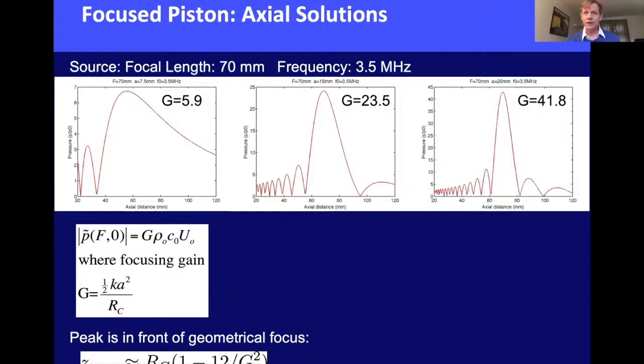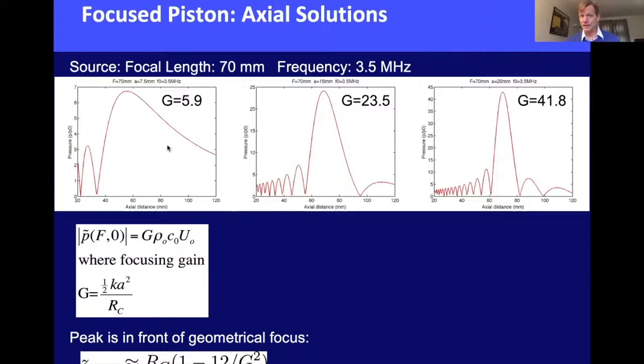Increasing the aperture to 20 mm raises the gain to about 42, producing a high tight peak almost exactly at 70 mm. The focal spot — defined by the half-pressure points — shrinks from covering more than 80 mm axially with the small aperture to about 20 mm with the large aperture. Larger transducers give much tighter focal spots for a focused transducer.